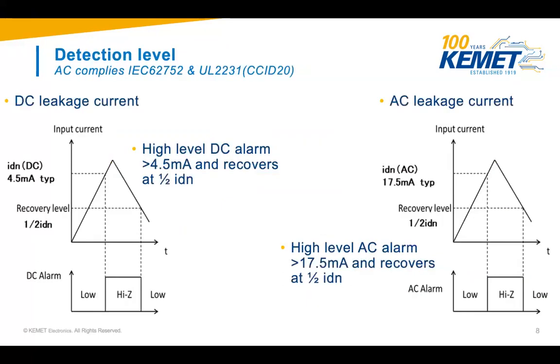And then there are, as you have maybe seen on the table, some different reaction times to cut off a certain leakage current. In this case, typically when there's a DC leakage of 4.5 milliamps, it will detect. That means the DC digital alarm signal will go to a high level, and it recovers once it's half of this typical current. So in this case, 2.25 milliamps, and then it would reset the alarm.